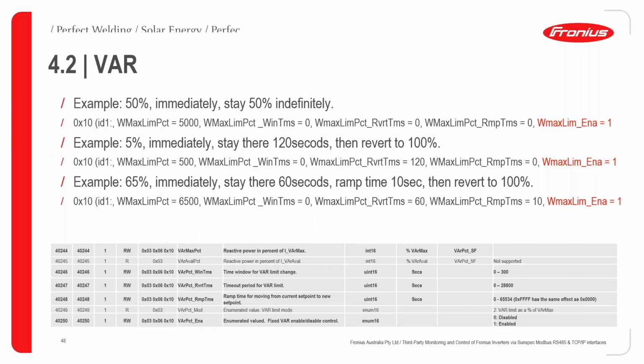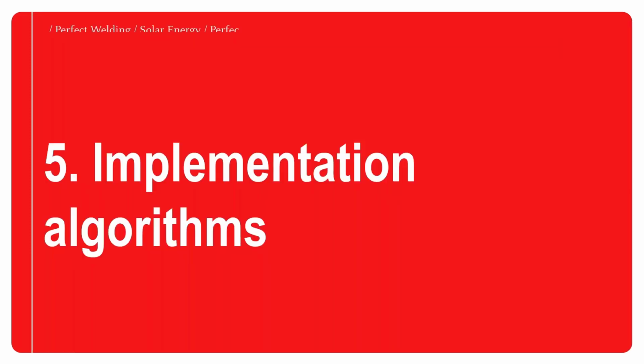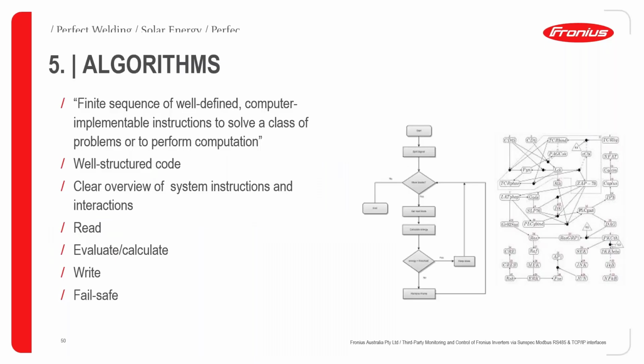Before I go further, something to bear in mind: you can't have VAR and power factor control at the same time. They're mutually exclusive, so you can choose. You can either control the power factor on the device or the VARs, because they're really the same thing. It depends on what control you want to get or expect from the device itself. Something to think about when you do your application.